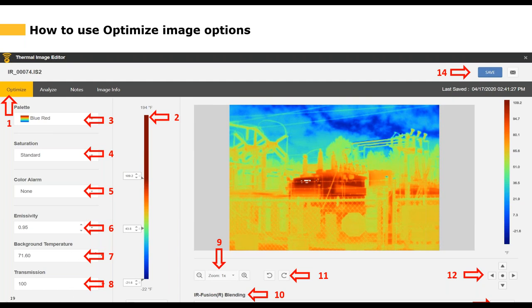Next we have Background Temperature, which is simply the ambient temperature — for instance, if you're in Florida and it's 95 degrees, you set the background temperature to 95 degrees. Transmission is an option for if you're using an IR window: you enter the settings specified on the IR window. This is a rare circumstance, but the option is available for customers who do use IR windows.